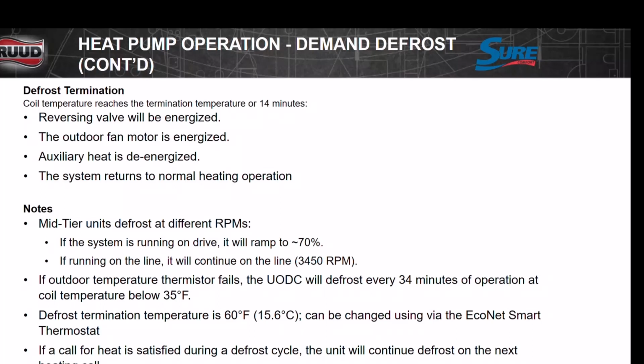The mid-tier operating RPMs are as if the unit's running on the drive, it will ramp up to 70%. If the unit is on the line, which means it's running through the capacitor, it's going to run at 3,400 RPM, which is where it hits high. Okay, that's the maximum RPM of that compressor. The outdoor temperature thermistor on the UODC, it will defrost every 34 minutes at an operating coil temperature of 35 degrees or below. And then terminate again at 60.